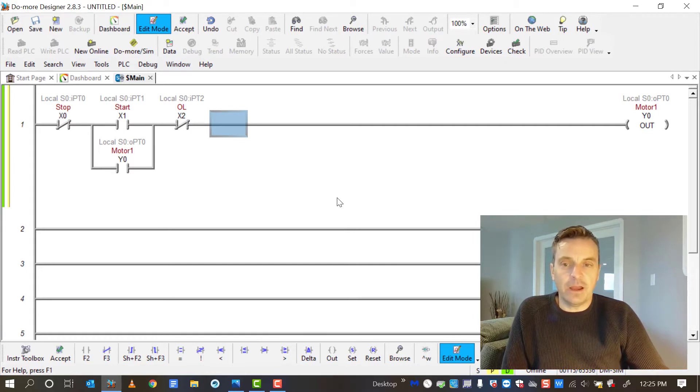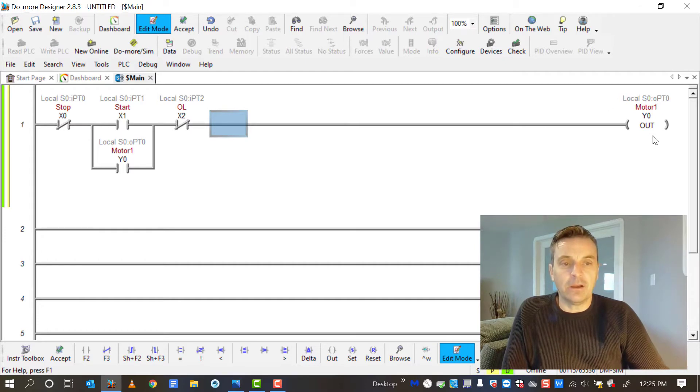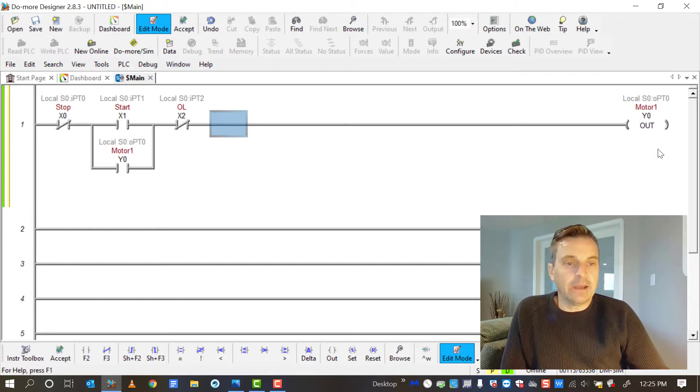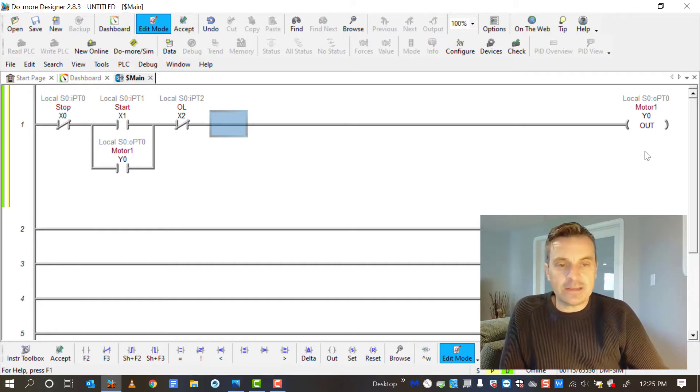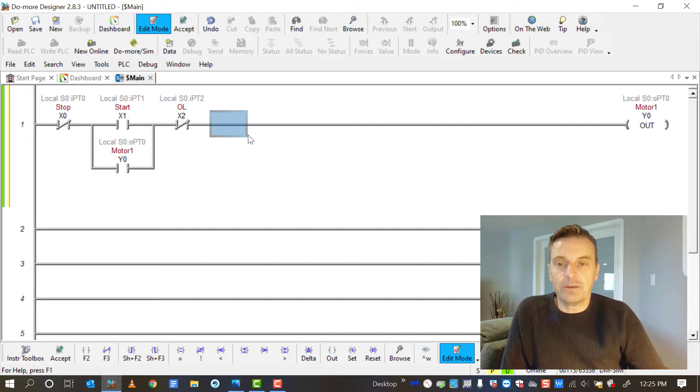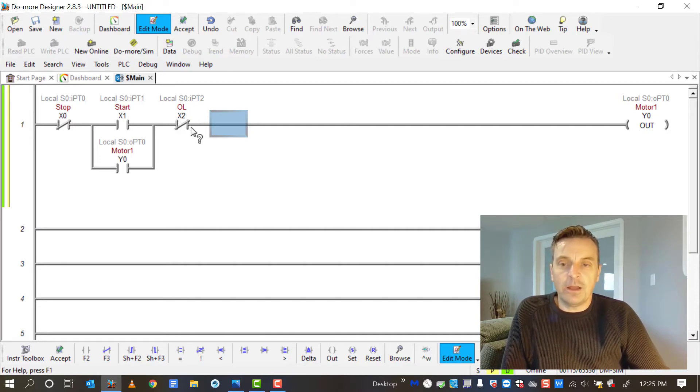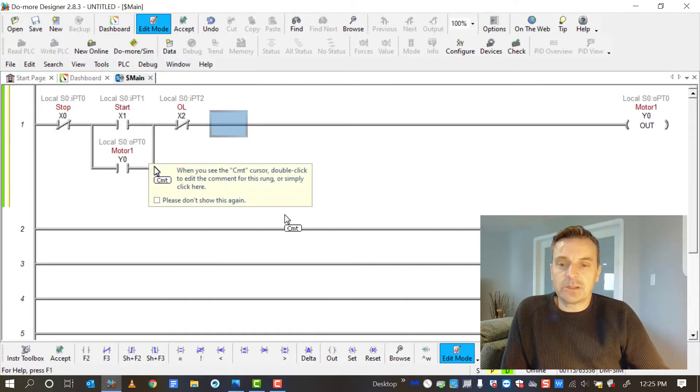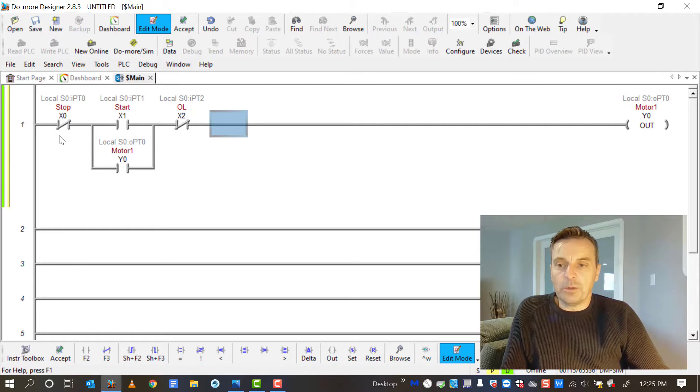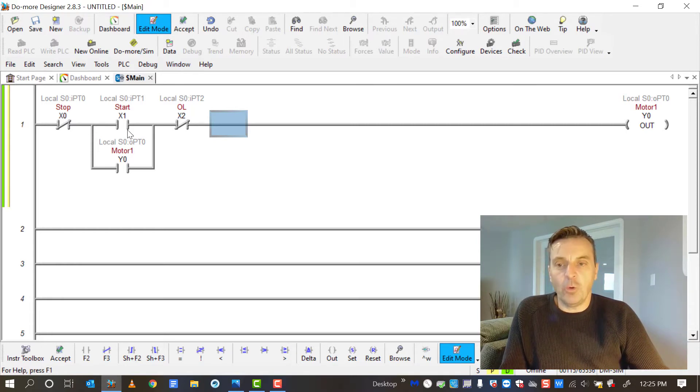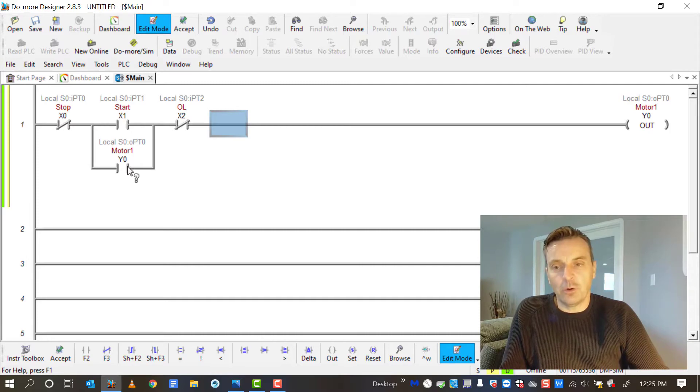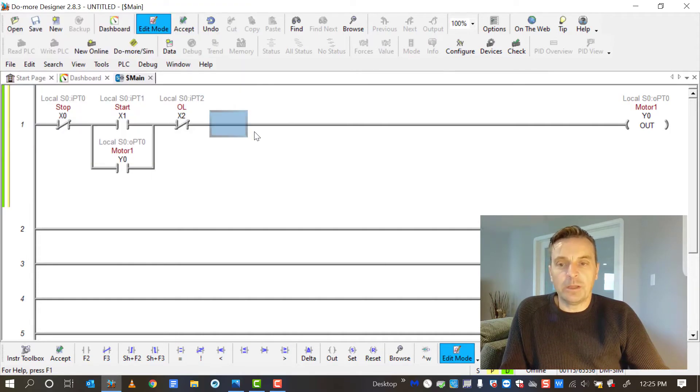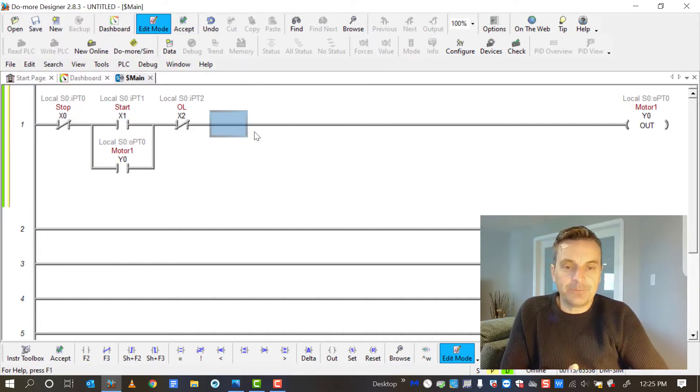If you try to do anything other than that, you're going to get error messages. In fact, it's pretty hard to write anything there. If you leave that blank, you're going to get an error message. So it has to always go to an output of some sort. So we put the overload contact here, and you can see that we've set these up just like we saw in the schematic. This was a normally closed, just like the normally closed push button. This is a normally open, like the normally open push button, normally open holding contact, normally closed overload contact.